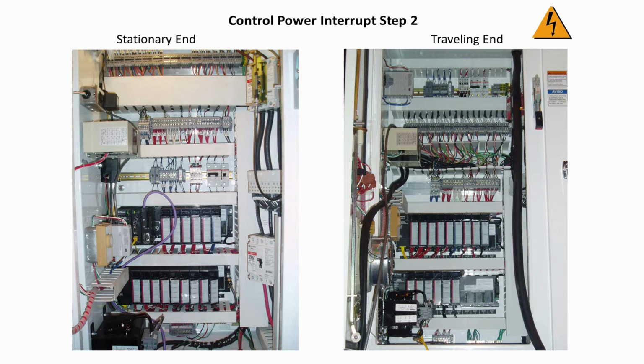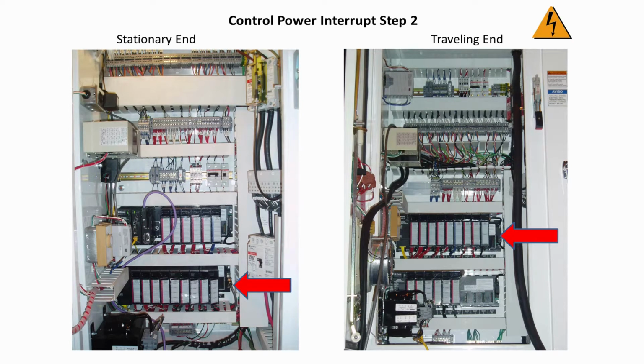Check number 4. If the run light is lit on the stationary end power supplies, then it should be lit on the traveling end power supplies. If it is not, check the cable that connects the PLCs of the stationary end to the traveling end PLCs. The cable runs through the cat track. Check it for tears, bulging spots, or worn spots. If it looks okay, then ohm the cable out, which connects to the bottom PLC rack on the stationary end on the far right-hand side of the rack to the top rack on the traveling end on the far right-hand side. If you find any tears, bulges, or other problems, replace the cable.